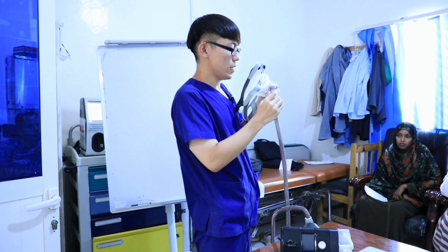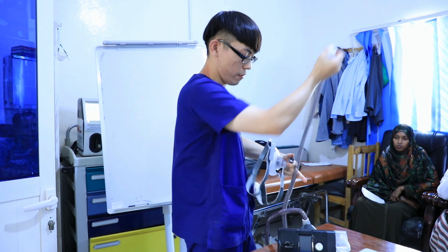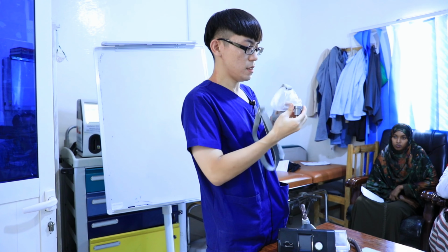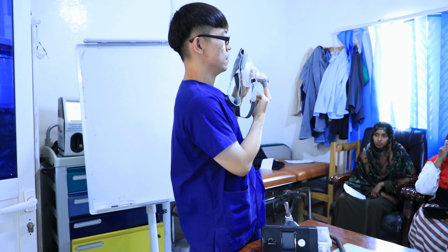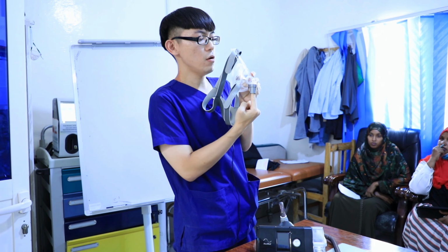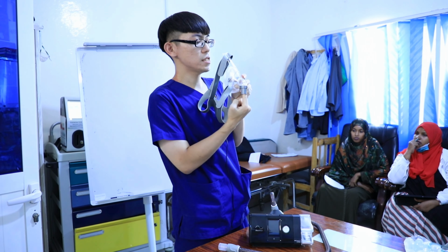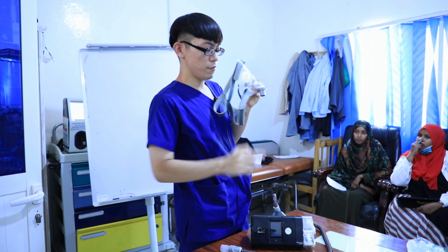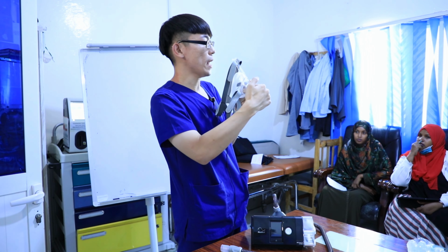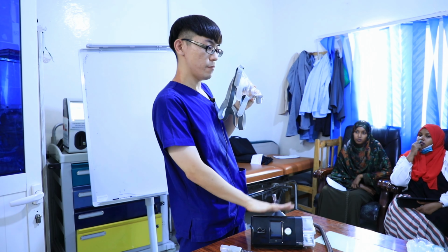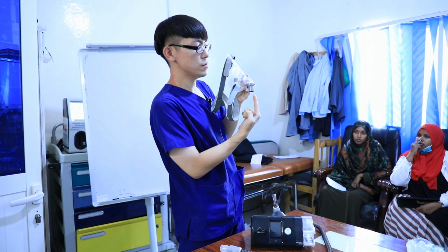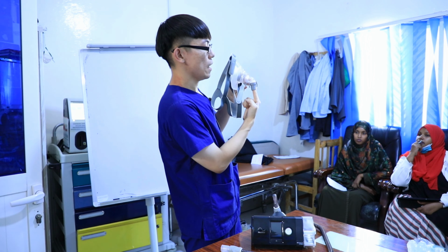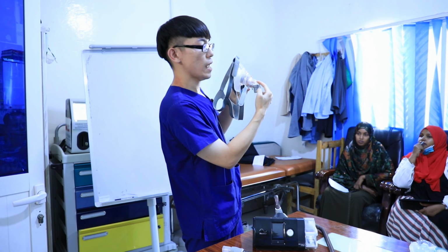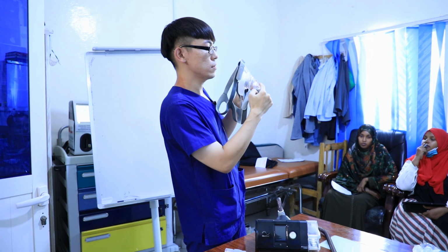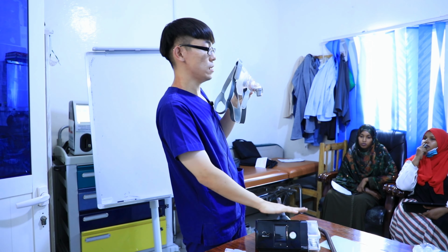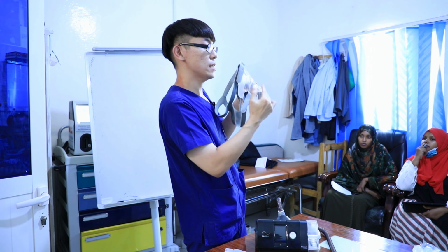Another one is that this part has a one-way valve over here. This is called the anti-suffocating valve. If the machine is shut down, the patient can breathe room air from this port. But if the machine is working, the positive pressure delivered from this side will close this room air port. So this port is just for when the machine is not working, so the patient can breathe room air and not suffocate.